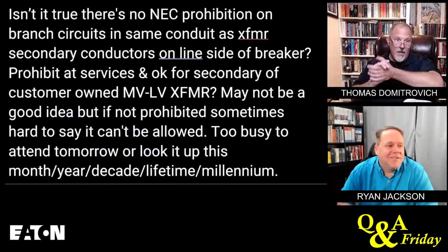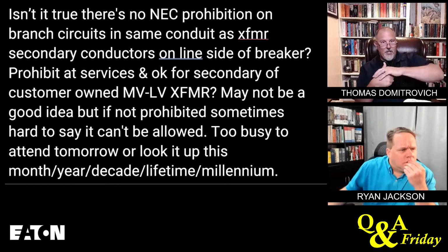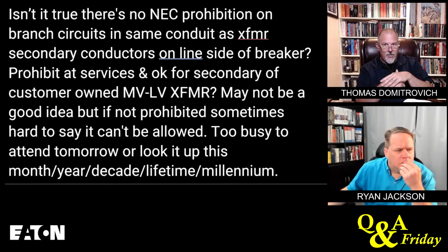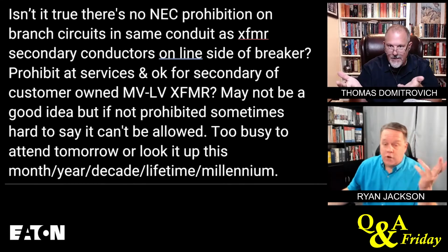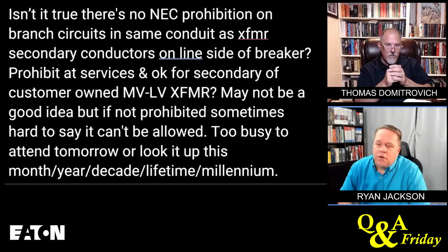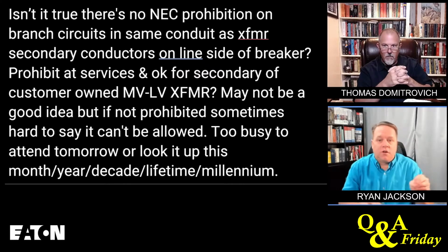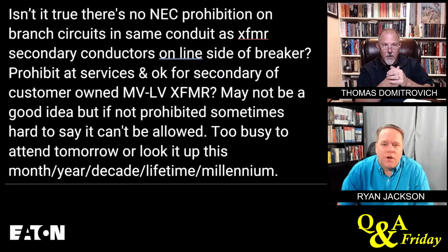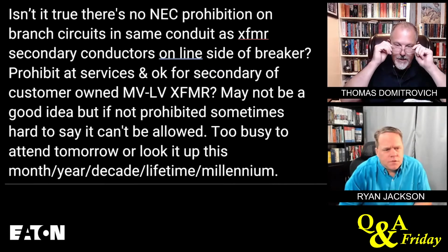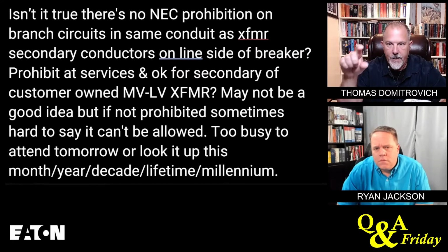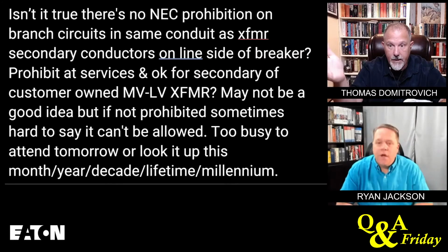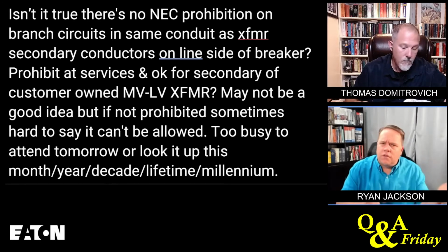Now here's a question: isn't it true there's no NEC prohibition on branch circuits in the same conduit as transformer secondary conductors on the line side of the breaker? Prohibited at services and okay for the secondary of customer-owned medium-low voltage transformers. I would agree with that, right? I don't think there's a prohibition. The only prohibition is service conductors and non-service conductors in the same raceway. Right. And with any conductors in the same raceway, you have to think about the voltage ratings of the insulation and all that jazz, right? Certainly. And that's in section 300.3(C), as in Charlie.